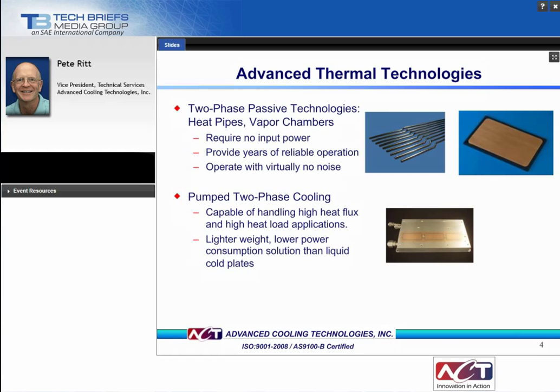The second group, active pump two-phase systems, offer important benefits over pumped single-phase liquid design. One important advantage is higher heat transport capability. The obvious benefit of the higher heat transport is the ability to handle high heat densities and heat loadings with reduced pump requirements, saving weight and energy while delivering a more uniform temperature across the evaporator surface. We will now examine both of these technologies in a little more detail.